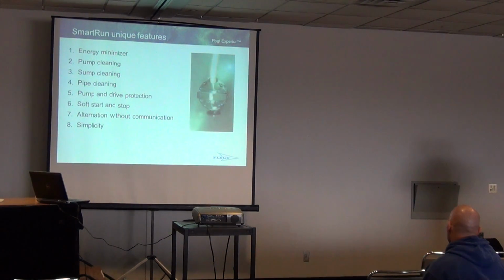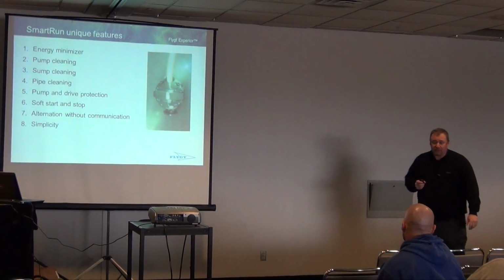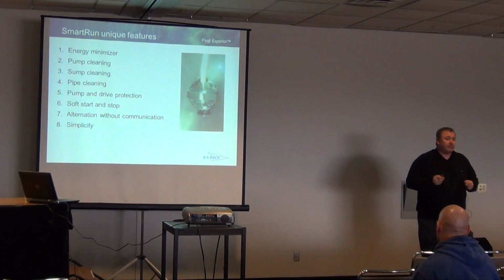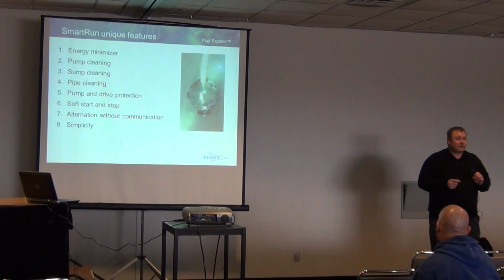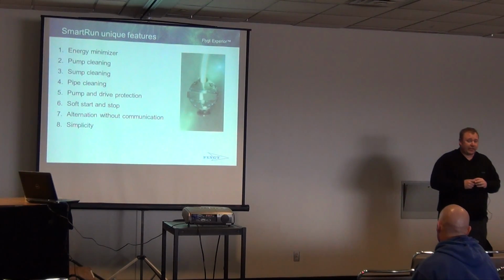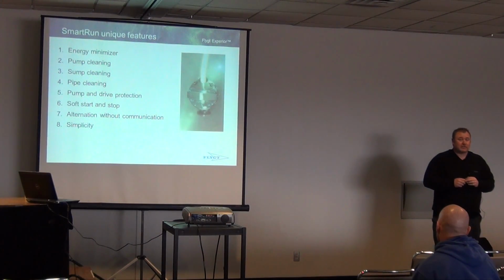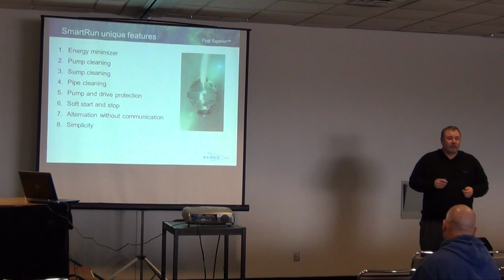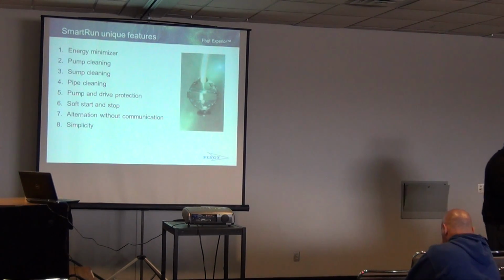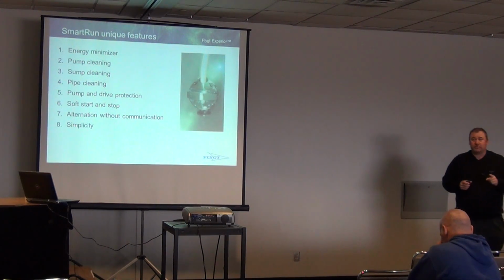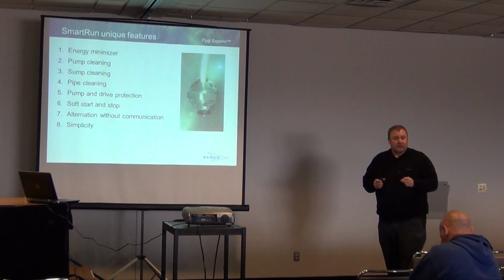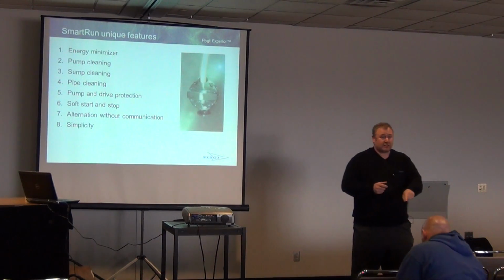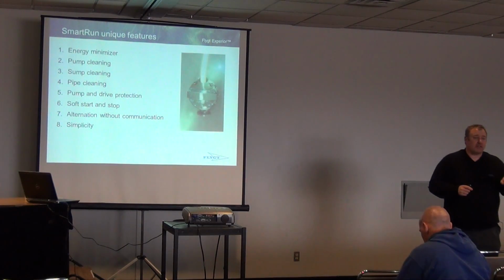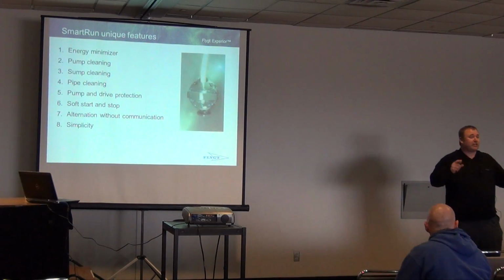Now, one of the things that we can do at Flygt, and with Electric Pump, the company that represents us, obviously, you know they represent us here in Minnesota and the Dakotas, is that the guys at Electric Pump have the ability to come to your sites and use what we call an energy savings calculator to come out and evaluate your current sites. And what they do is they look at your pump station, they determine how many hours that pump station is running in a year, they look at your power bill and determine what you're paying in kilowatt hour for power, they look at what kind of impeller you currently have in that system now, and they plug all this information into this energy savings calculator, and it basically creates a pie chart.